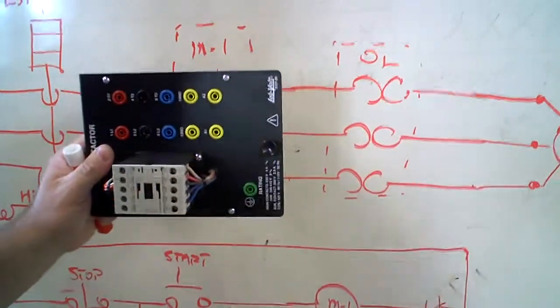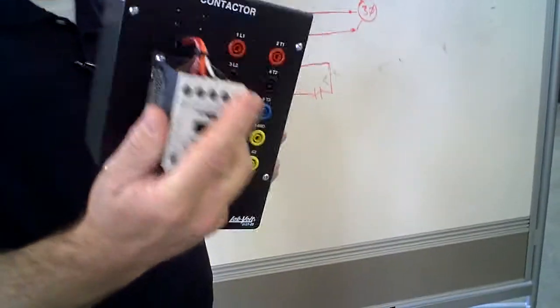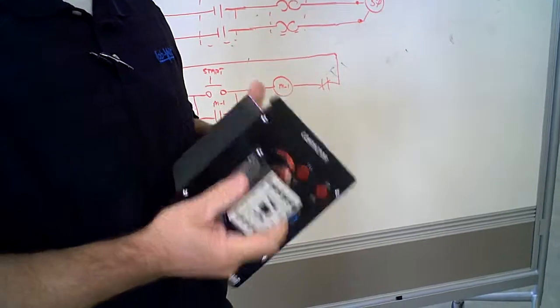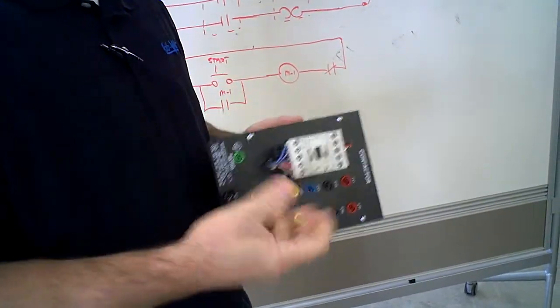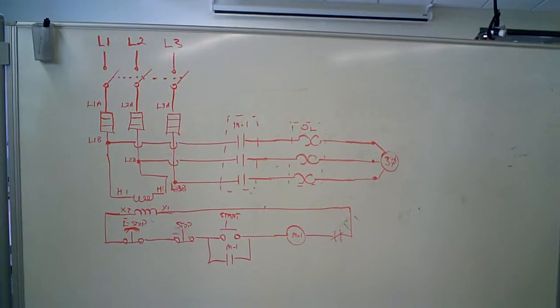So that's the contactor. A contactor is a magnetic induction device. It uses electrical current. When voltage is applied to the coil, it creates a magnetic field, closes the contacts just like a relay. So those contacts close and then hold them out.